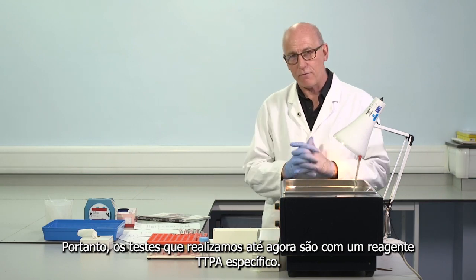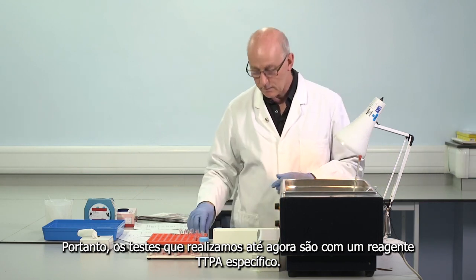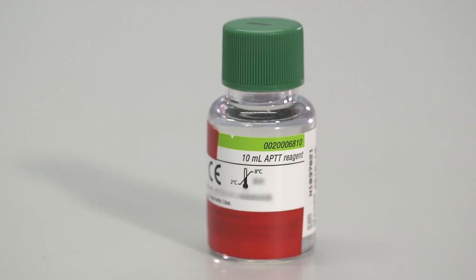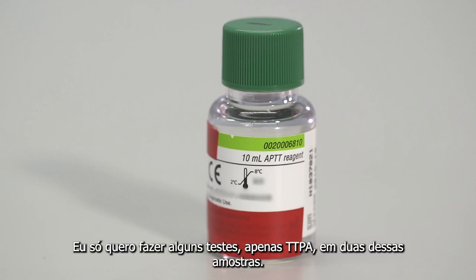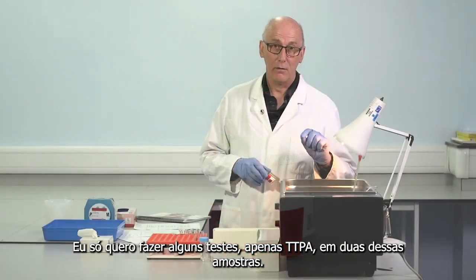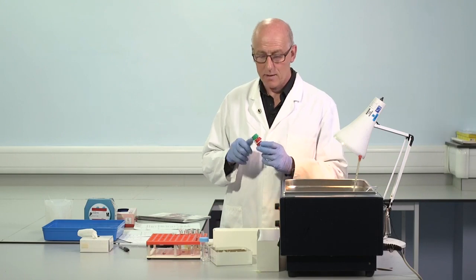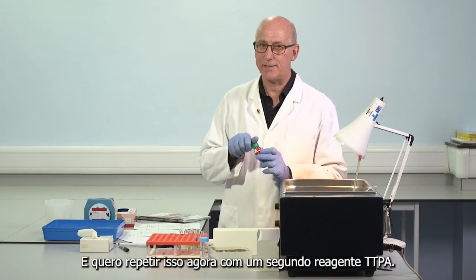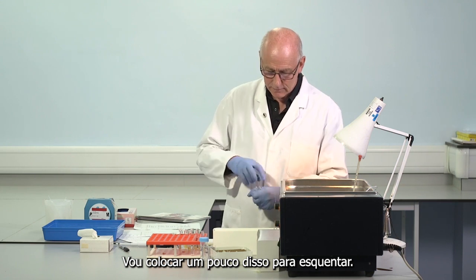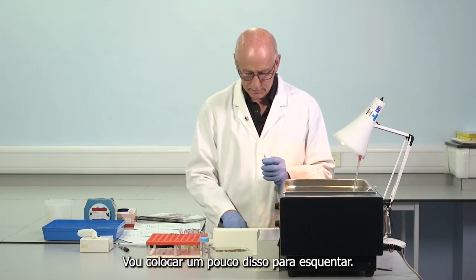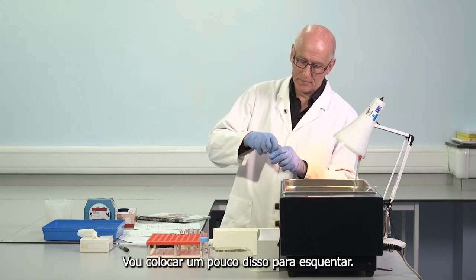So the tests we've performed so far are with one particular APTT reagent. I just want to do a couple of tests, just APTTs, on 2 of those samples. And I want to repeat that now with the second APTT reagent. So I'm going to put out some of this to be warming.